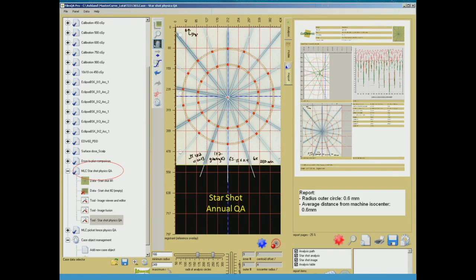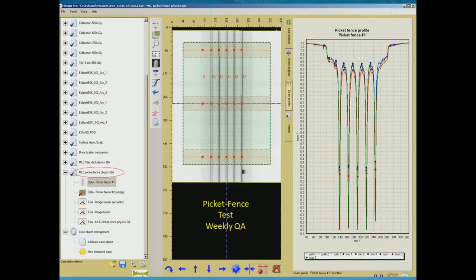Shown here is the star shot for machine QA. In this case, the radius of the outer circle is 0.6 millimeter, analyzed by the software. And here is the analysis of the weekly dynamic MLC QA, the picket fence test.